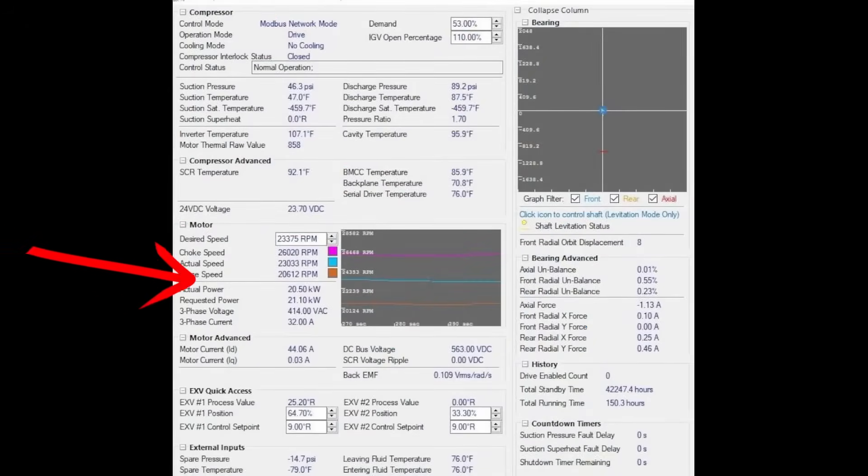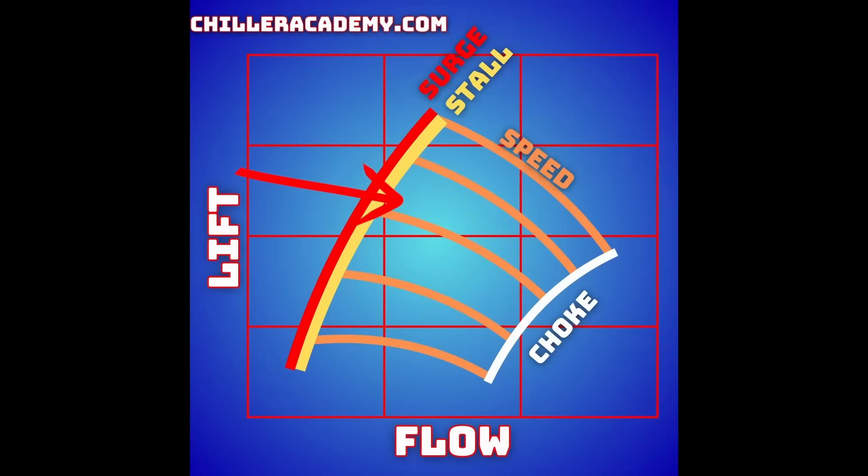In reference to our Turbocor here, if we have surge speed, if the actual speed lowers below this surge speed, meaning that we came over here and we just move straight to the left of this graph without actually reducing lift, which can happen, then we push into a surge state. Versus if we increase speed without adjusting our lift, depending on where we're at here, we have the potential to push over into a choke condition.